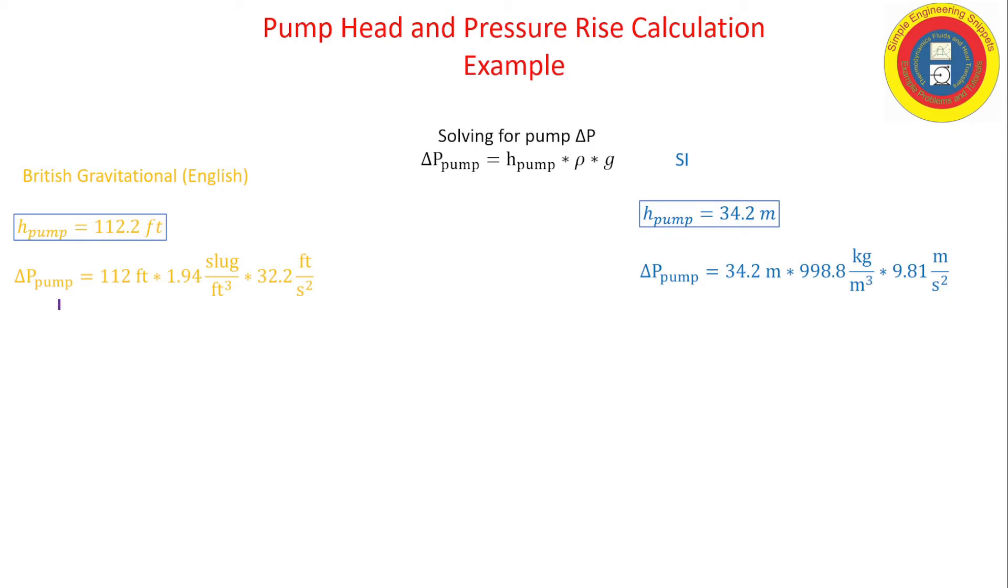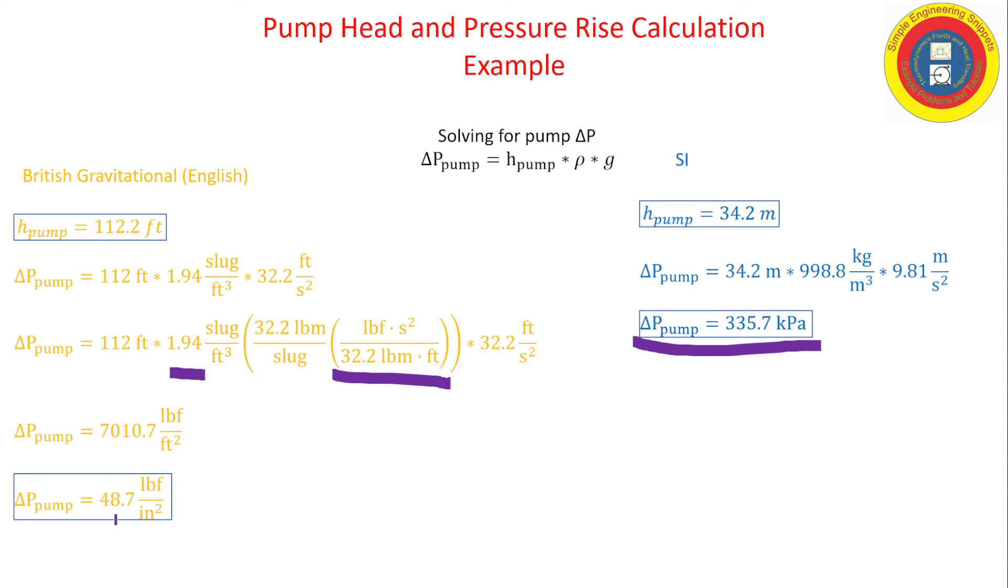We'll be doing it with the English engineer or British gravitational on the left and the SI on the right. As you can see, the SI, as is typical, pretty straightforward. Still got some work to do, some unit conversions, g sub c. And when we're done, we get the pressure rise is equal to roughly 49 psi and 336 kilopascals. Okay, so all that was done for a specific gravity of one.